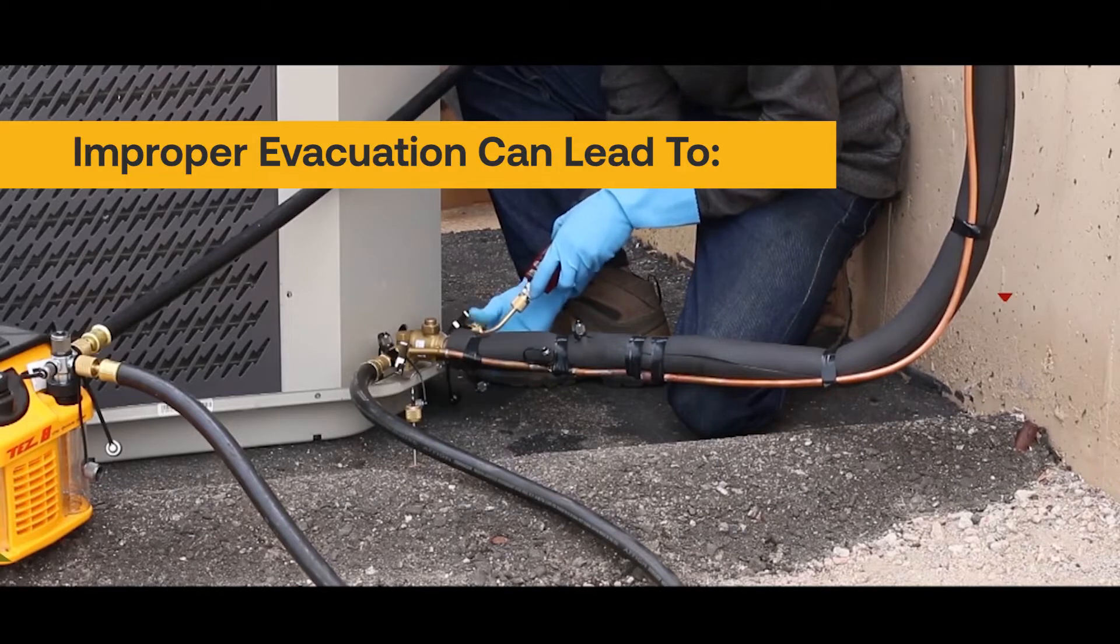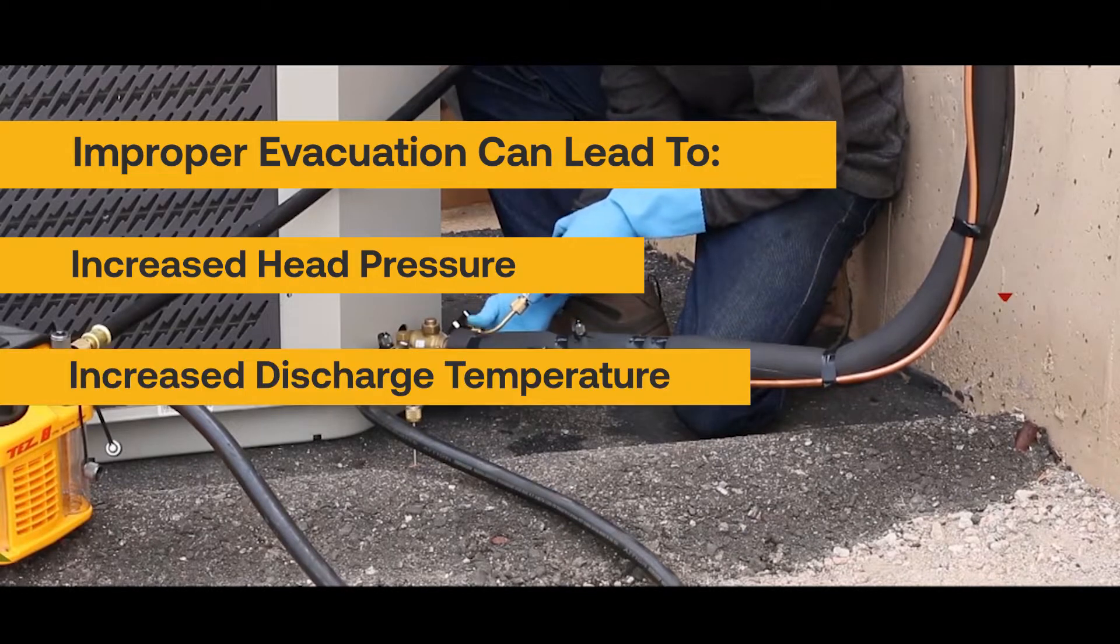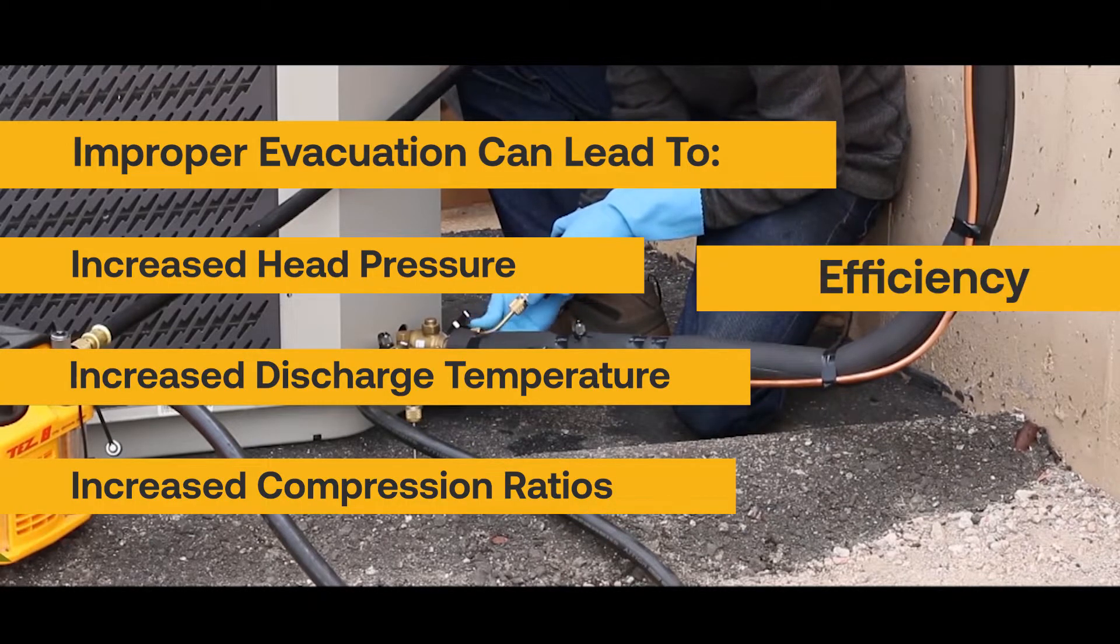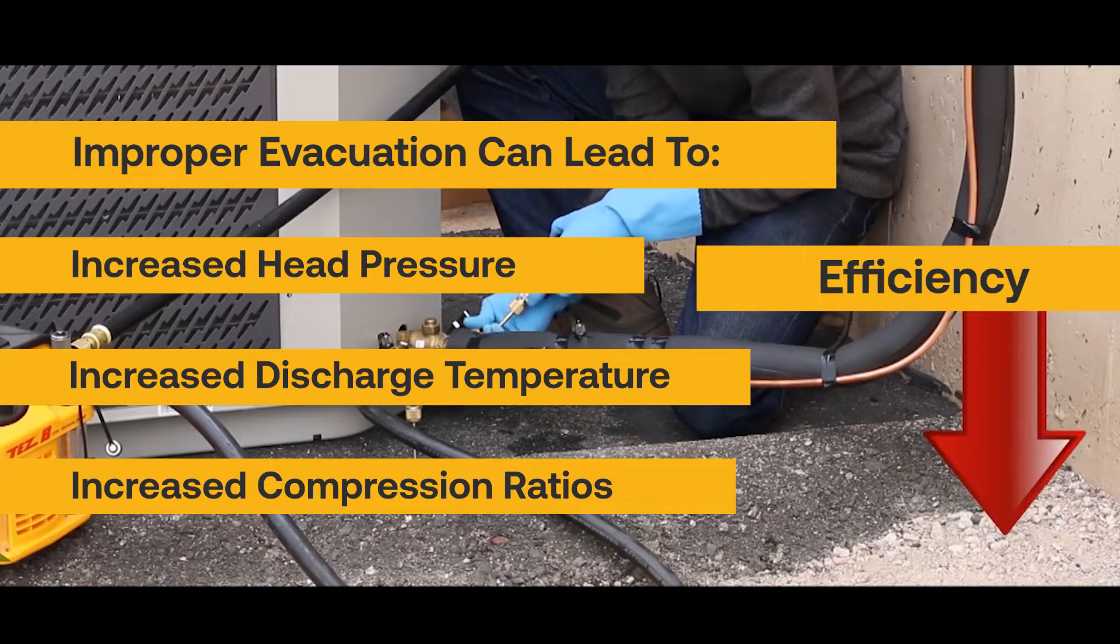When a system is improperly evacuated, contaminants and moisture left in the system increase the head pressure, the discharge temps, and compression ratios, decreasing efficiency.